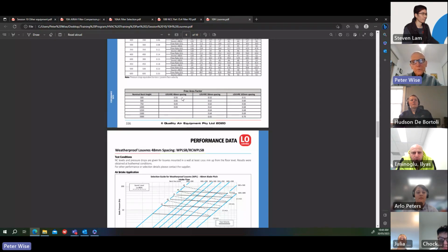And I'm raving on because it's important to be careful with these louvers. I did work on a job in Sydney that had been designed, the building was designed by the architect, obviously. I got involved in the project pretty late, after everything was installed. I arrived in Sydney and I was asked to go and check out things, why things weren't working and so on. We're having trouble with the outside air intakes, and it was because of the louvers.